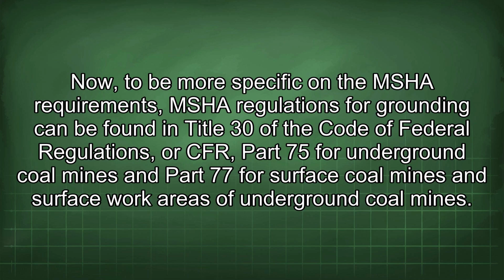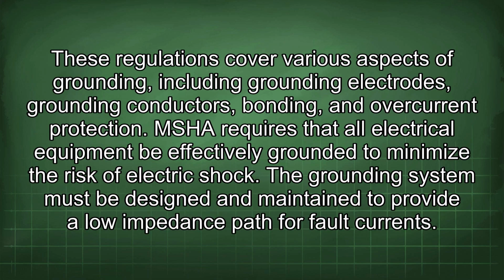Now, to be more specific on the MSHA requirements, MSHA regulations for grounding can be found in Title 30 of the Code of Federal Regulations, or CFR, Part 75 for underground coal mines and Part 77 for surface coal mines and surface work areas of underground coal mines. These regulations cover various aspects of grounding, including grounding electrodes, grounding conductors, bonding, and overcurrent protection. MSHA requires that all electrical equipment be effectively grounded to minimize the risk of electric shock. The grounding system must be designed and maintained to provide a low impedance path for fault currents.